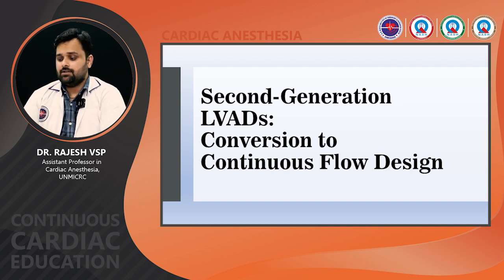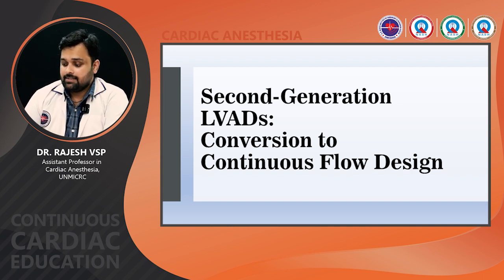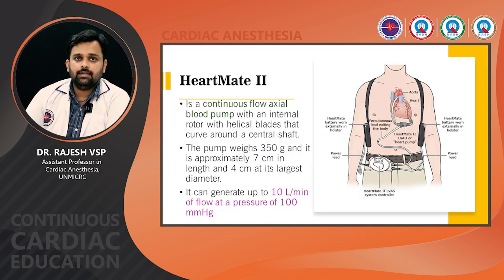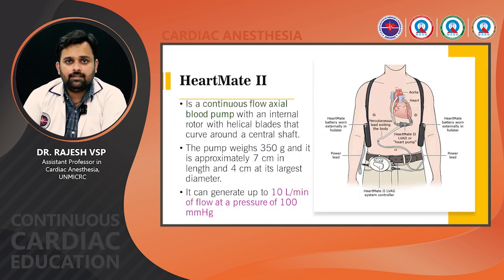Continuous flow pumps also have smaller drive lines and hence tend to have lower rates of drive line infection. In this comes the HeartMate 2. It is a continuous flow axial blood pump with an internal rotor, and it weighs around 350 grams, approximately 7 centimeters in length and 4 centimeters in largest diameter. It can generate up to 10 liters per minute of flow at a pressure of 100 mmHg.